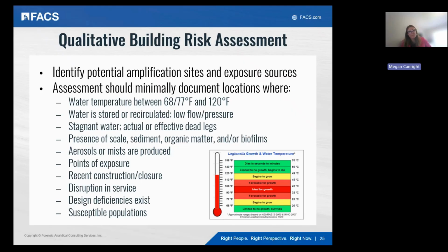The purpose of the qualitative building risk assessment is to identify areas of potential amplification and exposure within the building. At minimum, we go through the building identifying areas where water temperature falls in the growth range of organisms, areas where water is stored or recirculated, areas of low pressure, stagnant water, and dead legs—whether physically capped dead legs, engineered dead legs, or effective dead legs, such as a fixture that isn't used, creating a dead leg without an actual capped pipe.